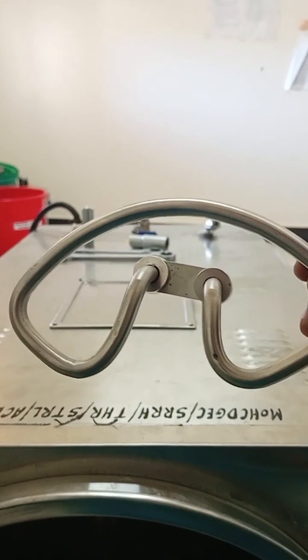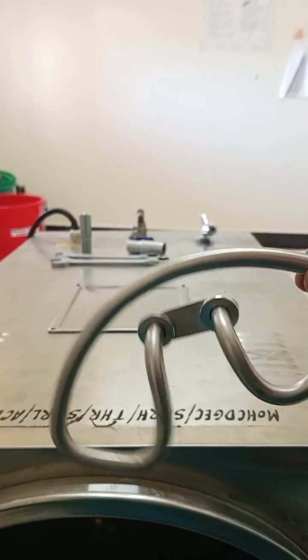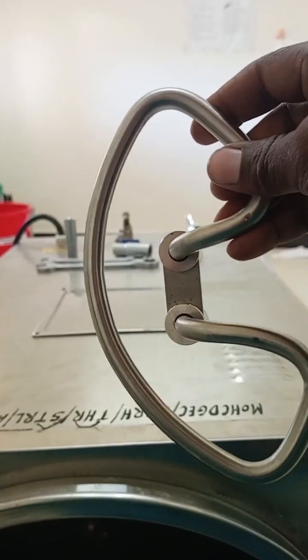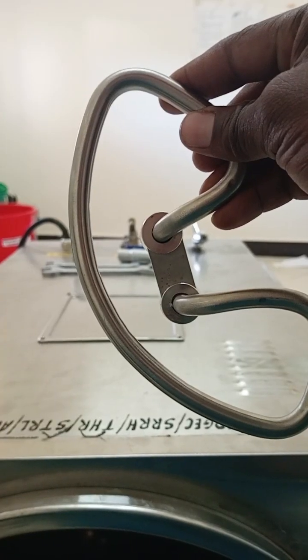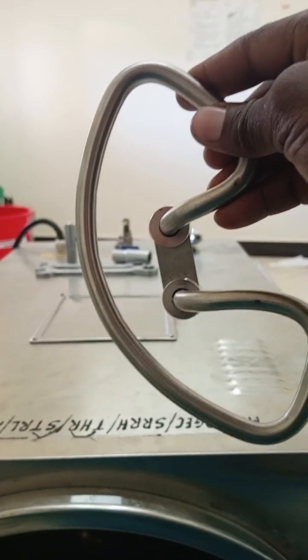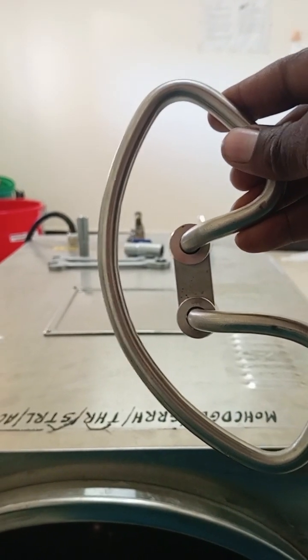Now when we are trying to replace this new heating element, we look at the protruding part of the heater, which should be directed to the middle of the autoclave. As you can see, the protruding parts of these elements are protruding to the center of the autoclave. Now this is a new heater. As you can see, the protruding part of this heater we must replace, but we must ensure that it is directed to the center of the autoclave, so that it fits properly and will not give out drainage. So let's go together.